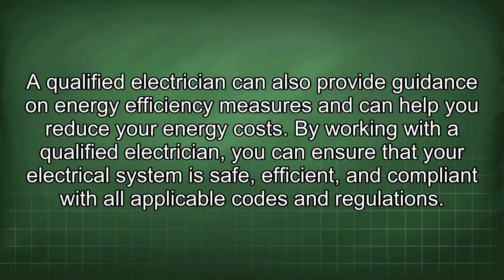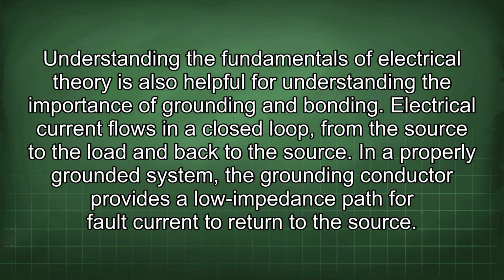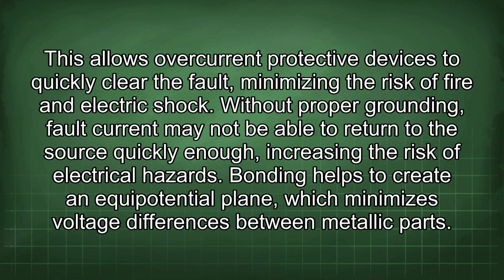applicable codes and regulations. Understanding the fundamentals of electrical theory is also helpful for understanding the importance of grounding and bonding. Electrical current flows in a closed loop from the source to the load and back to the source. In a properly grounded system, the grounding conductor provides a low impedance path for fault current to return to the source. This allows overcurrent protective devices to quickly clear the fault, minimizing the risk of fire and electric shock.